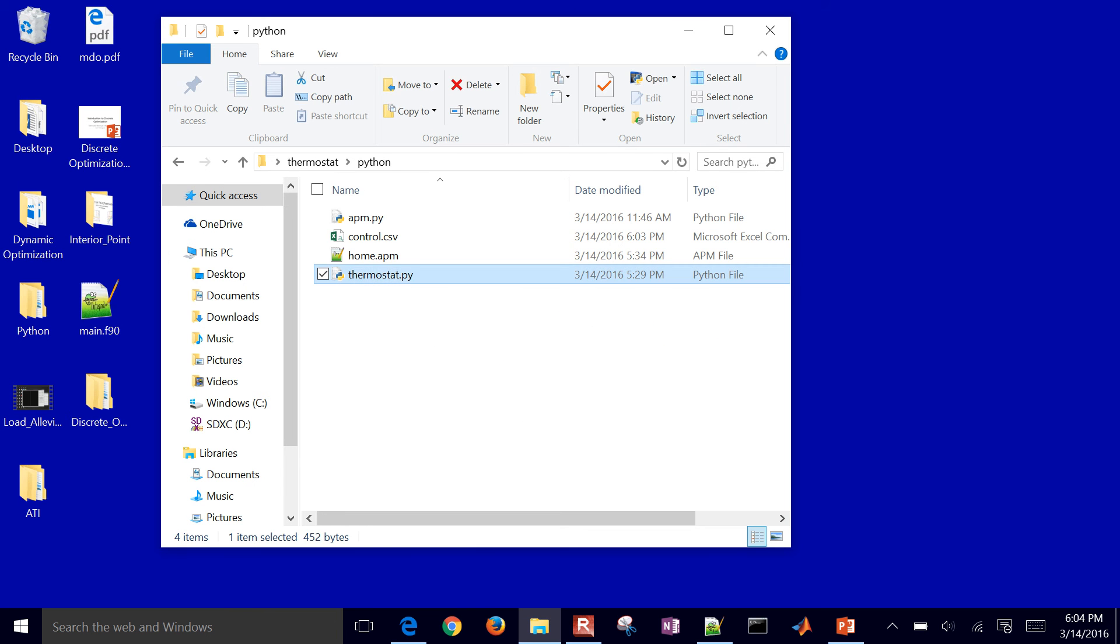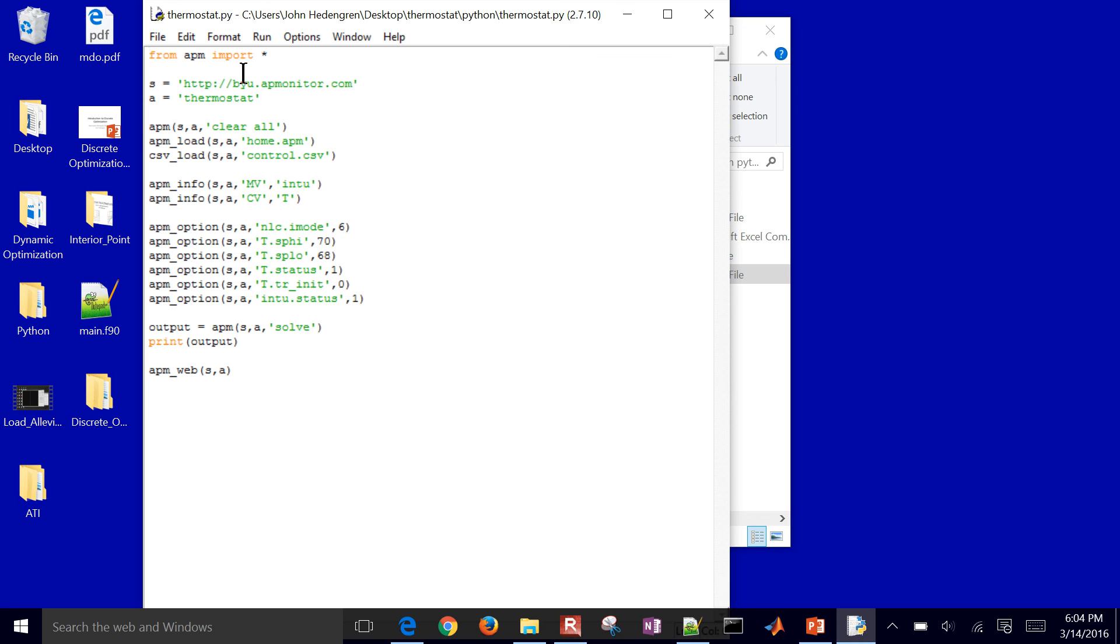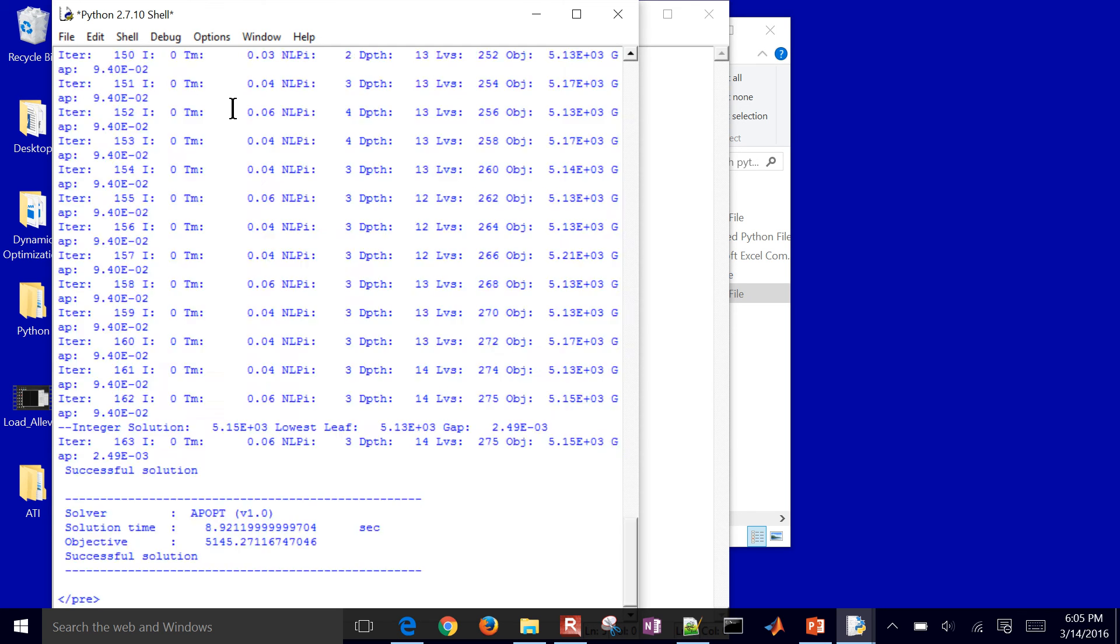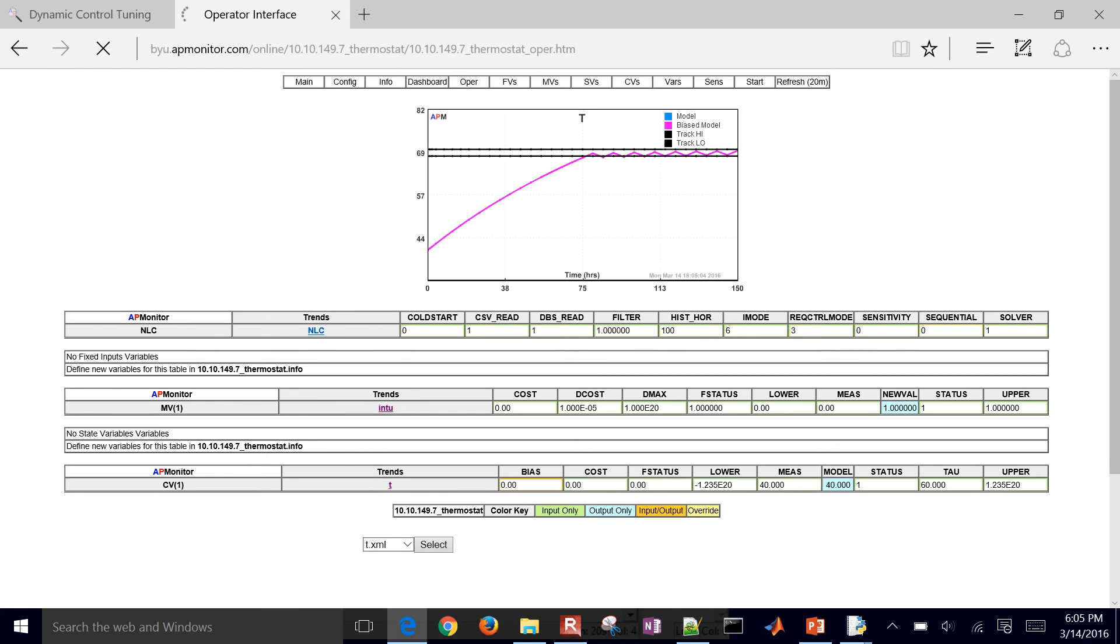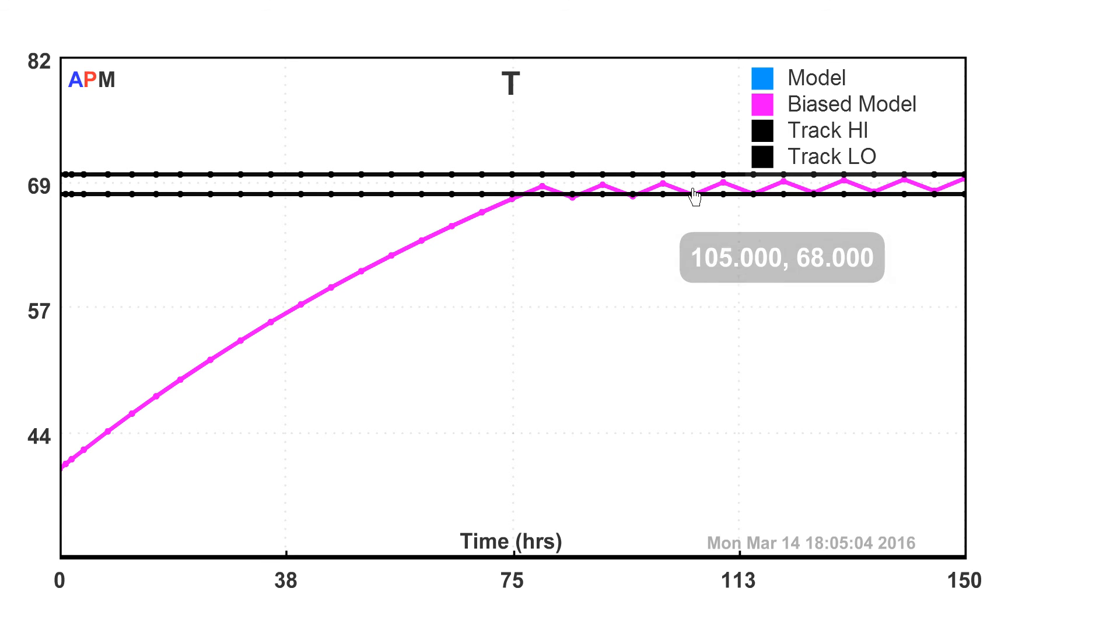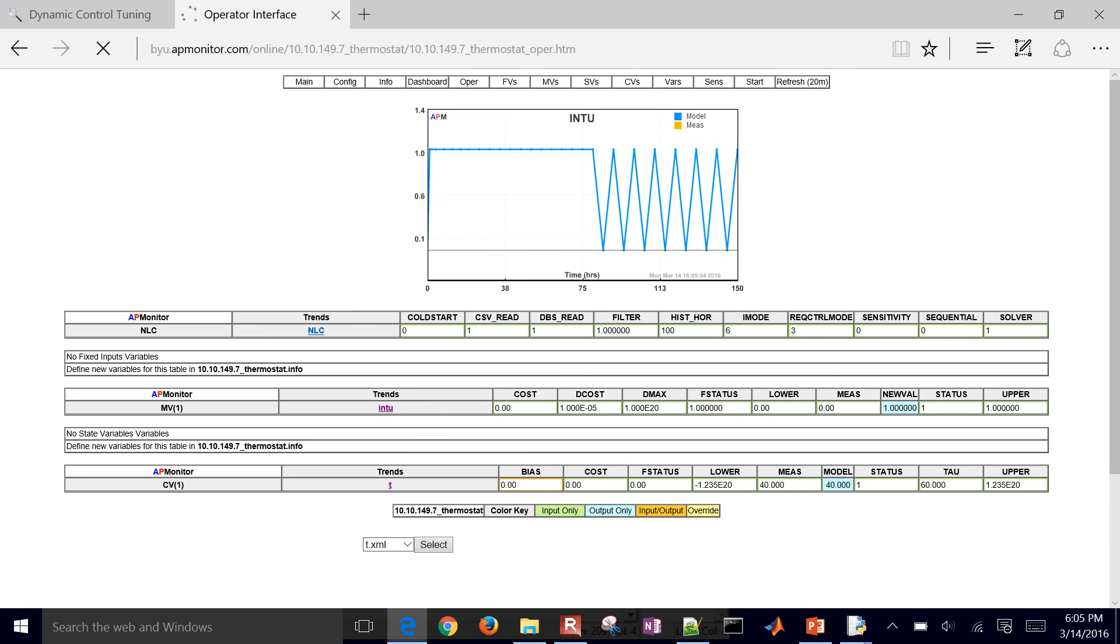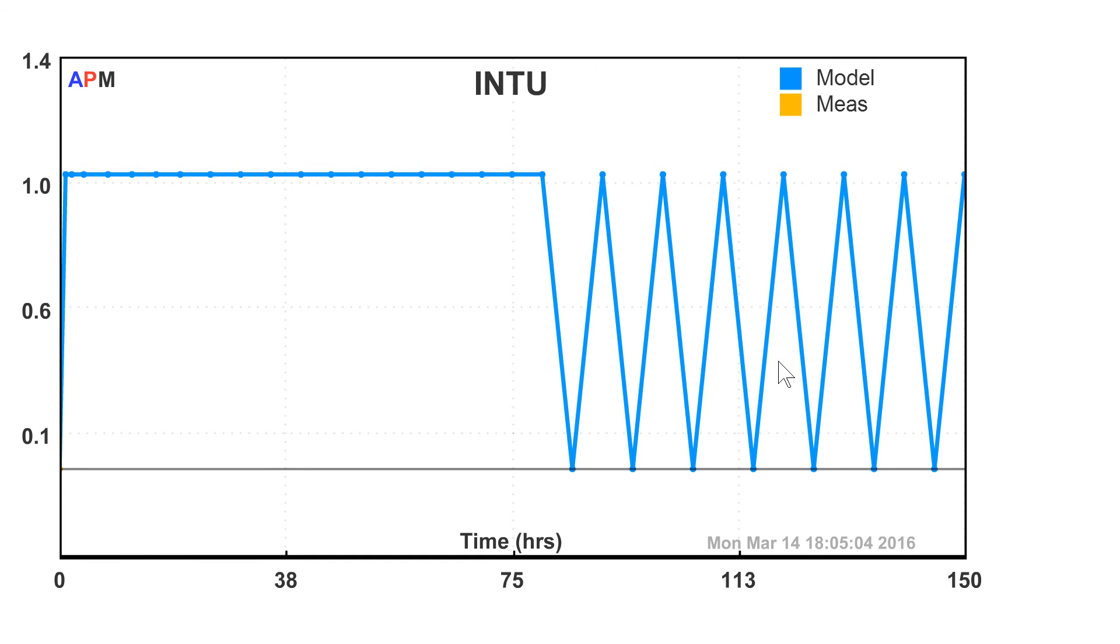And I'll run it. So it's going to take a few seconds to optimize and then we'll see what it wants to do for the temperature profile here. So this is the optimal heating profile. It heats up the home and then it turns on or off and keeps it within that dead band. And if I select, this is what the heater did. It turns on and off every about 5 minutes just to keep within that 2 degree dead band.